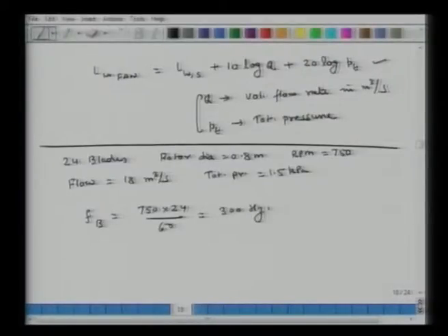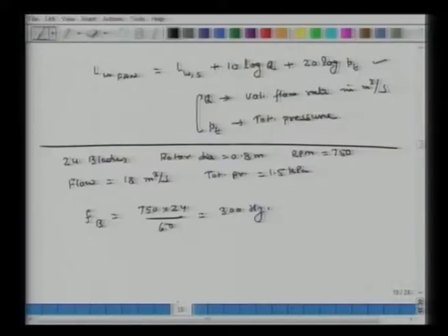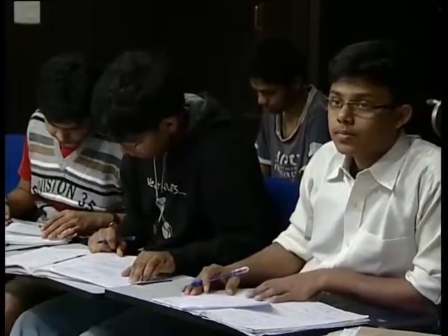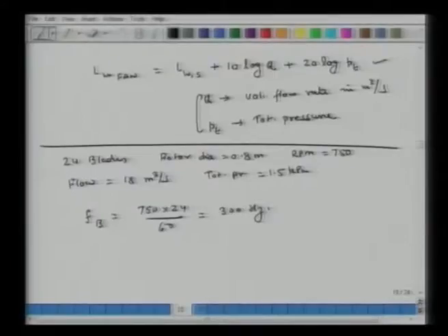What is LWS for this fan, the specific sound power level? This fan is radial curved forward. So, in the table, for the forward curved fan, which row should I pick? The last one, right? Forward 98, 98, 88, 81, 81, that row.